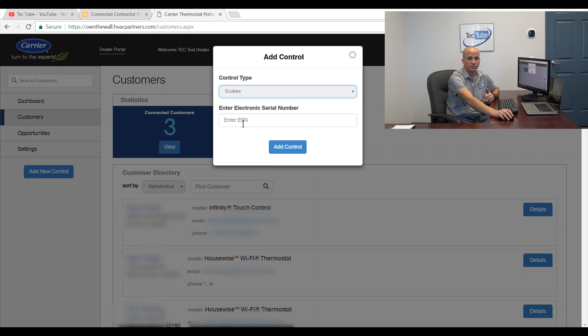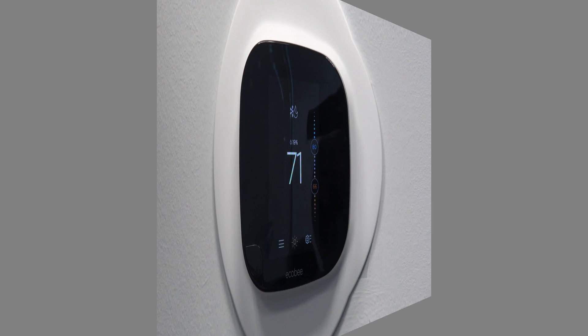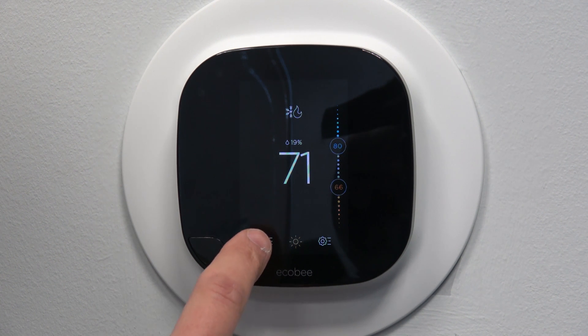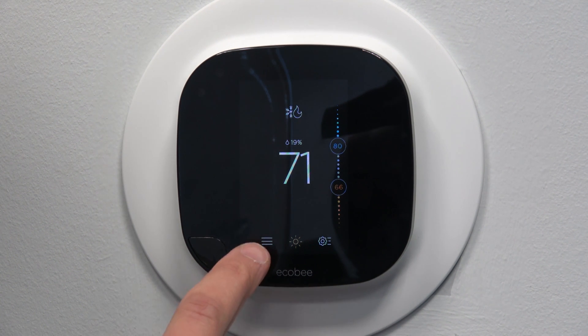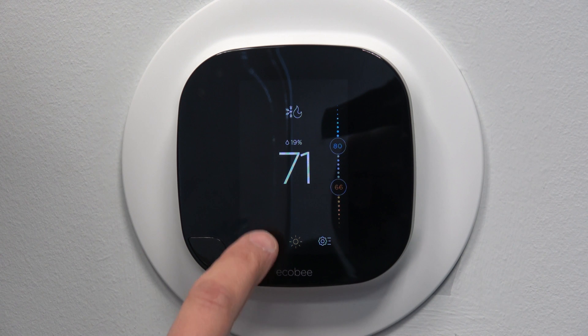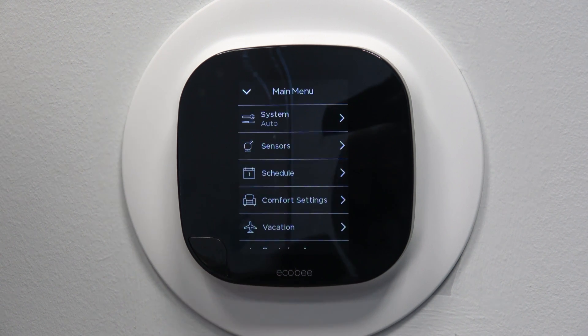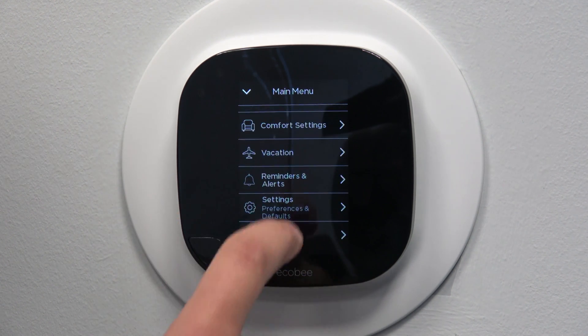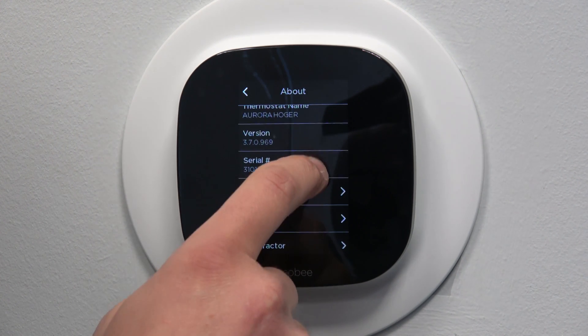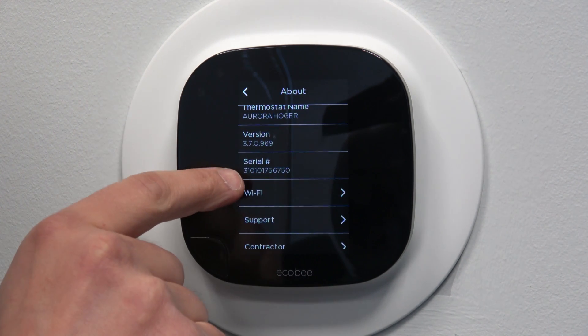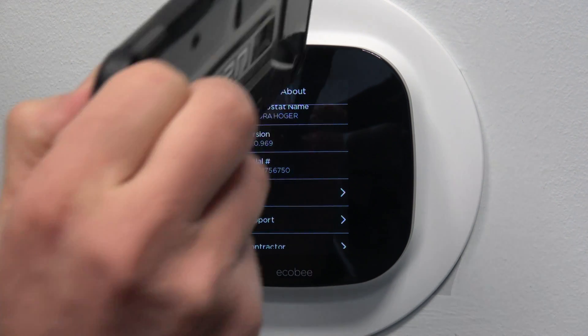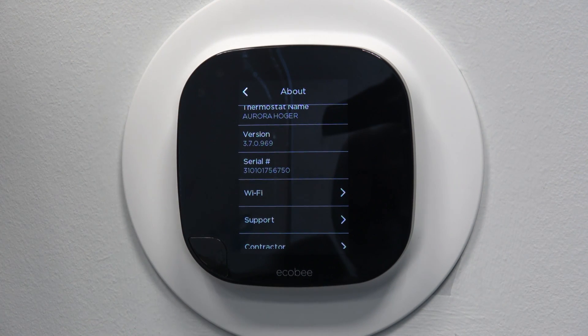So for Ecobee it's asking me for electronic serial number. So we need to go over to the thermostat and navigate to that screen to get that number. So let's do that now. On the Ecobee stat we'll click down here to the little, some guys call it the hamburger menu, but the little folder. We'll scroll down to the very bottom where it says about. Click on that and then down here, serial number. So we can either write that down or we can take a picture of it with our camera phone either way and we'll have that number.